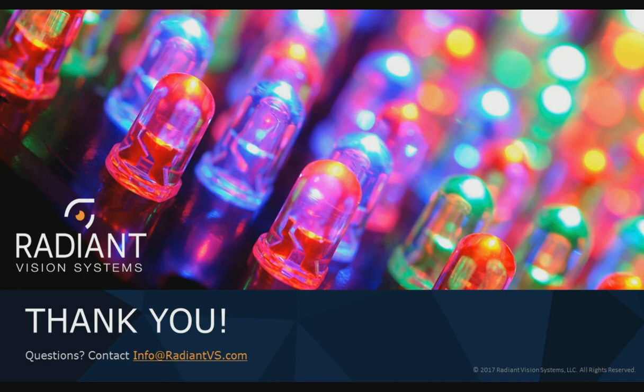Yeah, the software is written to interface with our Prometric imaging colorimeters or our imaging photometers. So you can use any of our released imaging colorimetry or photometer products. The I-Series is going to be a colorimeter and is going to be able to measure color for each of those point measurements, pixel by pixel.